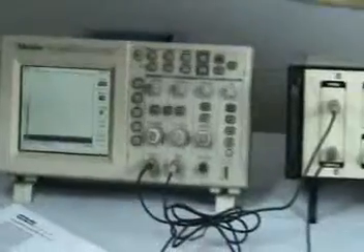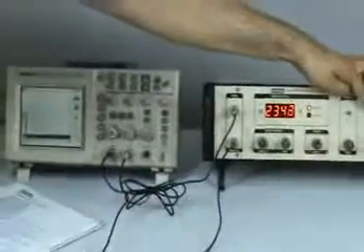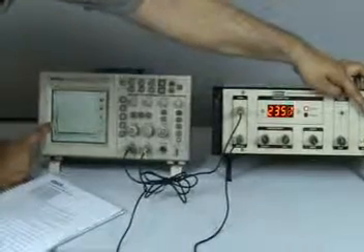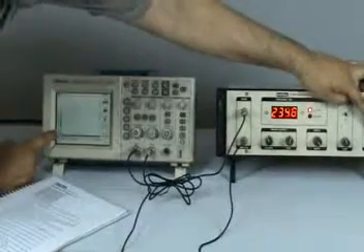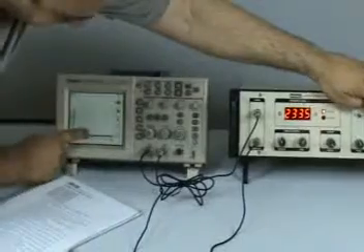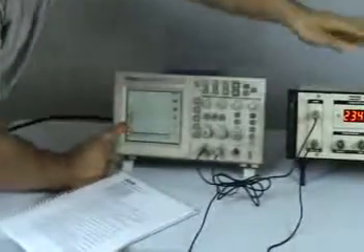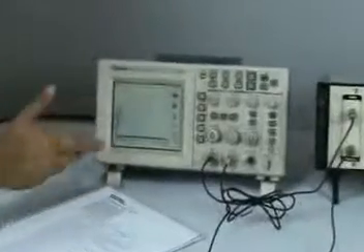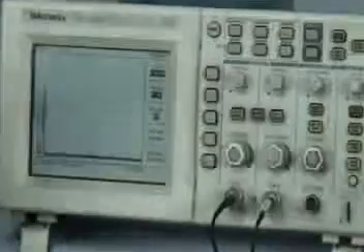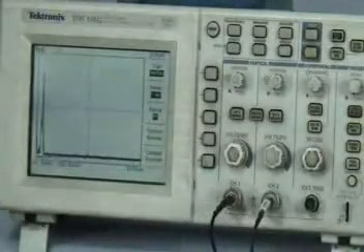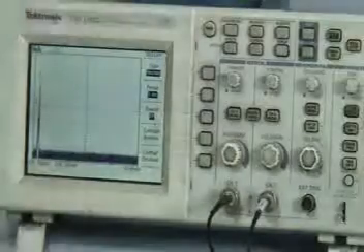We have also provided a video filter. Now you see, the moment the video filter is enabled, the video is being filtered out and very small signal levels which were up till now being drowned in the noise floor of the equipment can be made visible. Certain modulation characteristics can be enhanced by using the video filter. We'll move to the next experiment.